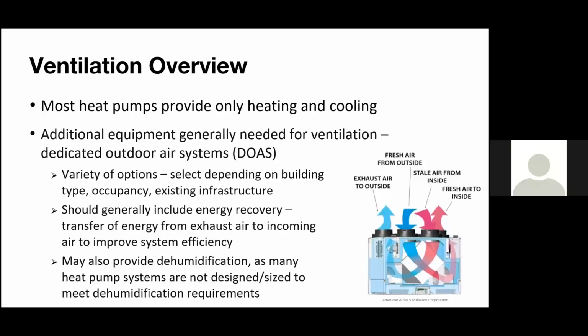And then the other way around, if you are worried about dehumidification, I know a lot of people are, it's very humid in the New England area. As we could see 2 weekends ago, it was pretty miserable overall. But if you're worried about dehumidification, let's say it's a 90-degree day, 70%, 75% humidity, what you can do is, off the wheel, bring that temperature all the way down to 55 degrees, which basically takes that moisture completely out of the air. And then we're able to use a reheat coil, a DX coil, to heat that back up to room neutral air. So that is also a method.